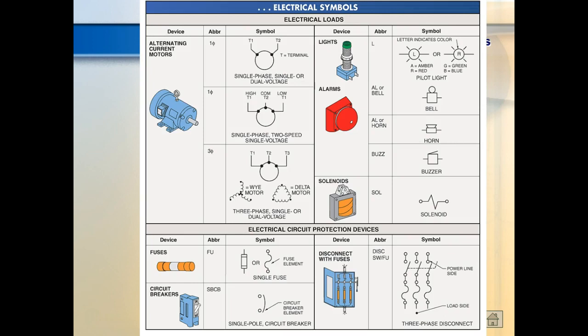So it sounds like those disconnects are like y'all's. Yeah, we don't have a bladed disconnect, we have a relay disconnect, so there's a relay up here. But ours are fused, and the fuses are exactly what they're showing. We have 3 fuses inside our disconnect, and we're going to make measurements inside it. We're going to simulate an open inside our disconnect, do this stuff in there, and we'll get to see the actual relay and stuff.